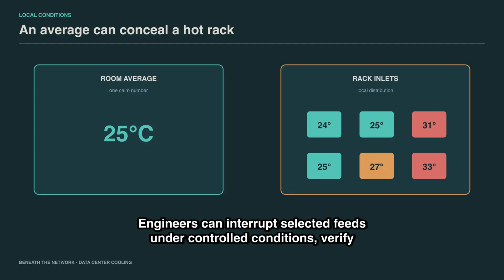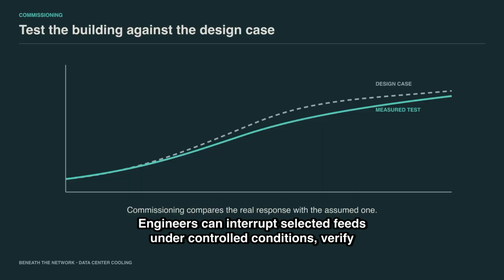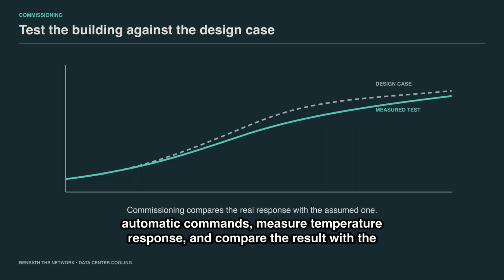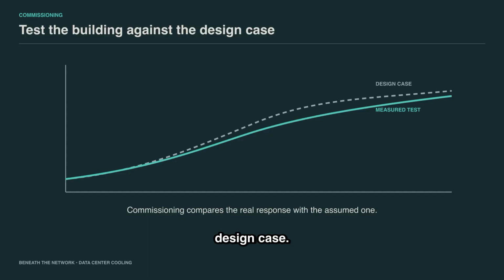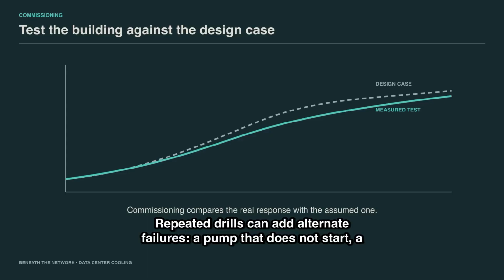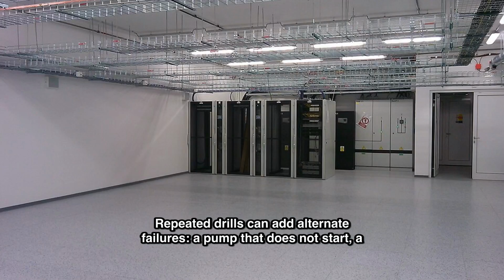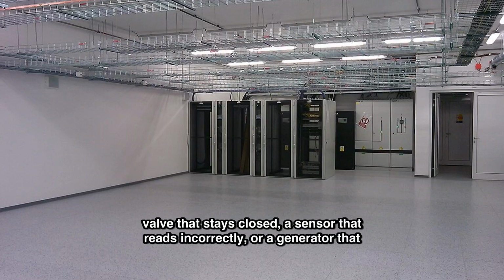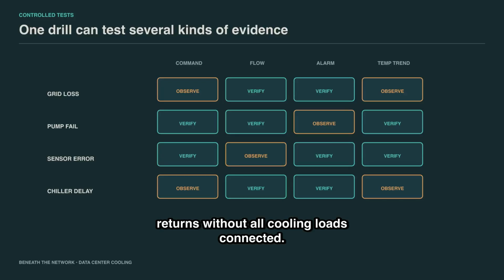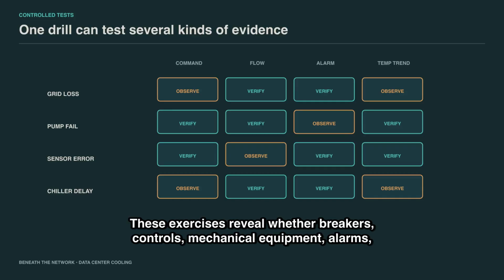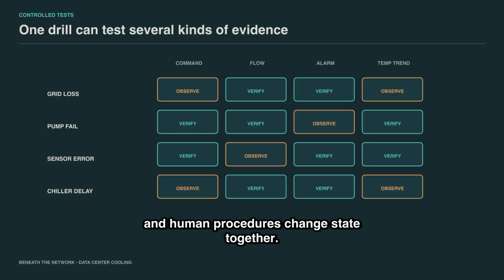Engineers can interrupt selected feeds under controlled conditions, verify automatic commands, measure temperature response, and compare the result with the design case. Repeated drills can add alternate failures: a pump that does not start, a valve that stays closed, a sensor that reads incorrectly, or a generator that returns without all cooling loads connected. These exercises reveal whether breakers, controls, mechanical equipment, alarms, and human procedures change state together.